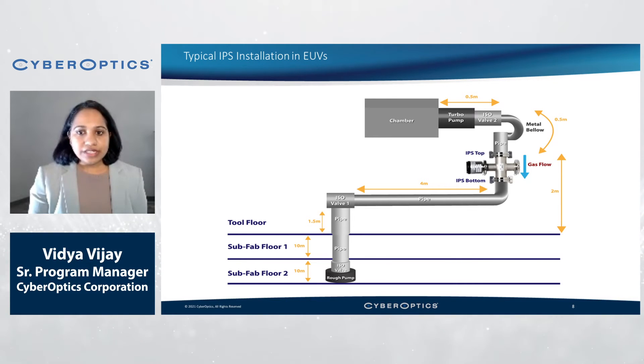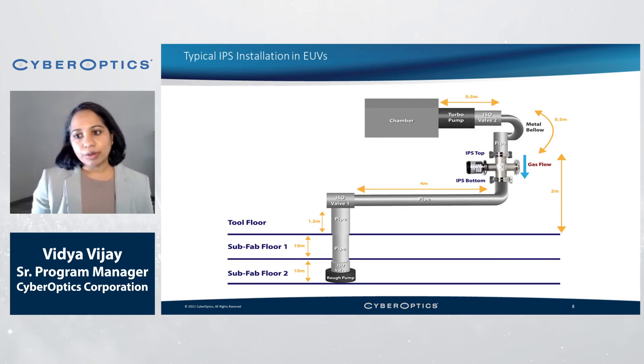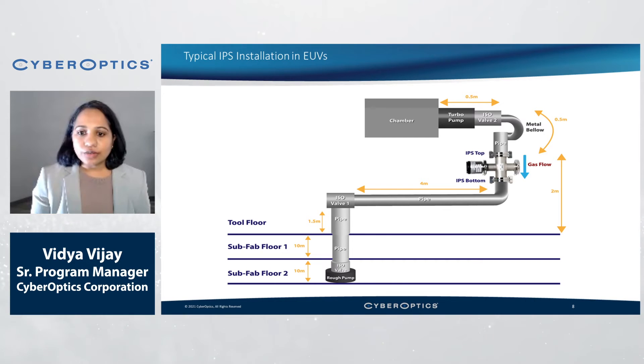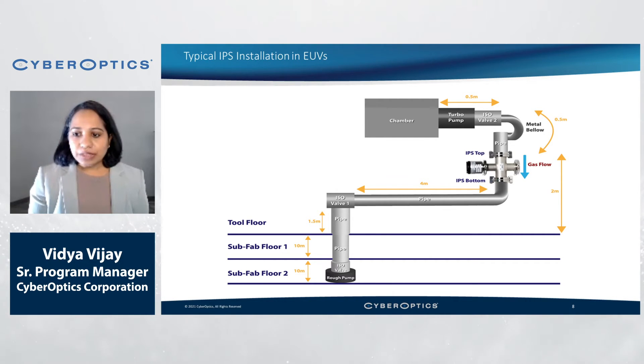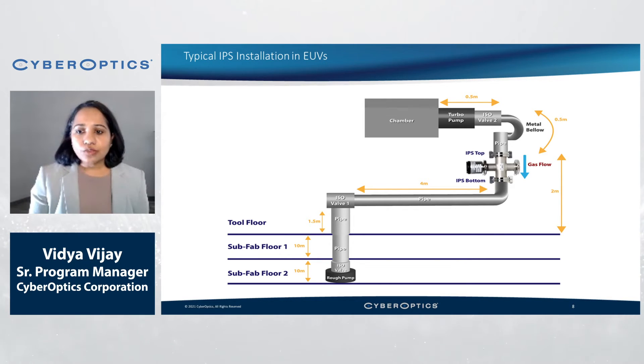Here is an example of an IPS installation at an EUV site. The IPS is usually placed in the vacuum line between the high vacuum pump, typically a turbo pump, and the roughing or fore pump. In this configuration, any particles generated in the system are concentrated and conveyed into the IPS by the turbo exhaust gas stream. However, the IPS sensor head can be placed in any area of the vacuum system where particles are expected to pass. Experience has shown that IPS will typically see the majority of particle events when the system pressure is changing or when items are moving inside the system.